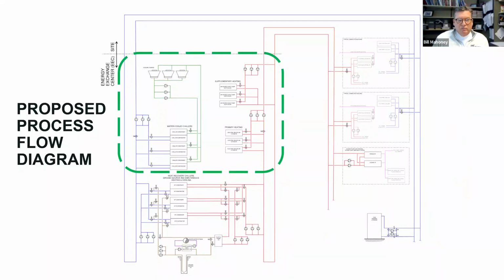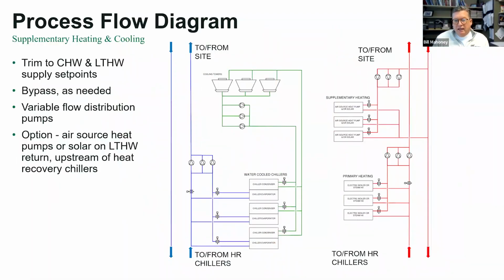Here we go. So we're moving down in the plant, and we just came from the heat recovery chillers. We did what we could with them, and now we draw off and run through condensing boilers or heat exchangers using the steam from the cogen plant. And now we can send it out at 140 or higher if you wanted to in this configuration, back out to the buildings here. And then on this one side, we put a sidecar connection here on the cold side when it's coming back.